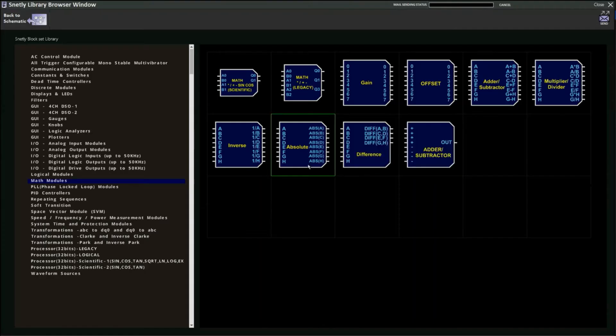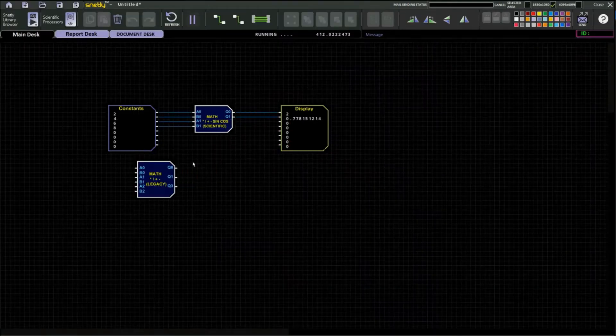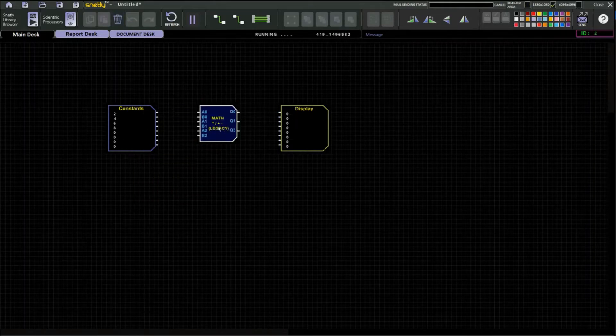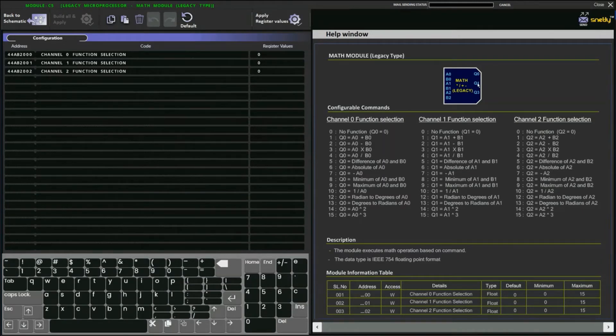Next, we take the math function in legacy mode, which uses the legacy processor. The difference between legacy and scientific is that in legacy we can only perform arithmetic operations — no trigonometric functions. However, this block performs three operations simultaneously with three separate outputs. The register values go from 0 to 15, and each function number gives the same operation but on different output channels.